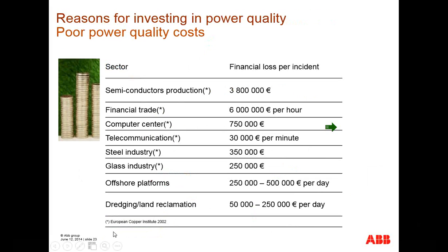This is some financial data which was published by the European Copper Institute in 2002. We can see that per incident the losses in the semiconductor industry are about 3.8 million euro. Financial trade is also about 6 million euro. Computer center, it is 7.5 lakhs euro. Telecommunication, about 30,000. Steel industry, 3.5 lakhs. So sometimes if it's a data center or some semiconductor industry, the losses are enormous if we do not consider power quality as part of the initiative. And as Mr. Manoj rightly pointed out, the APQI has taken this initiative.